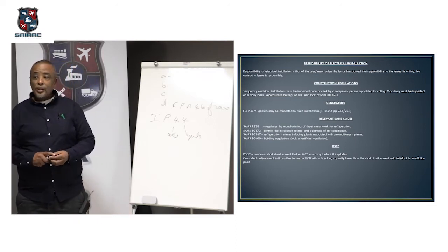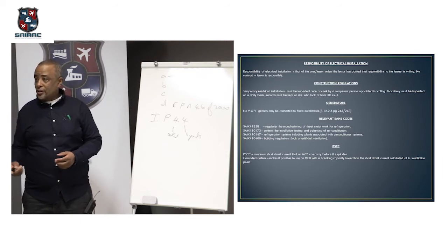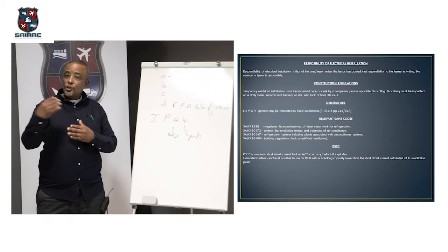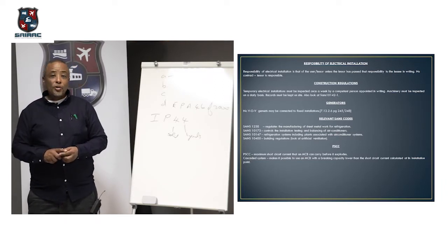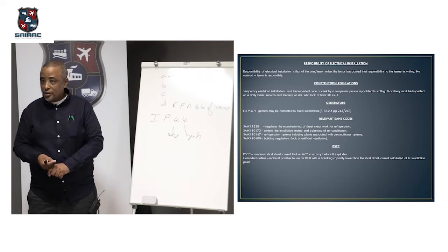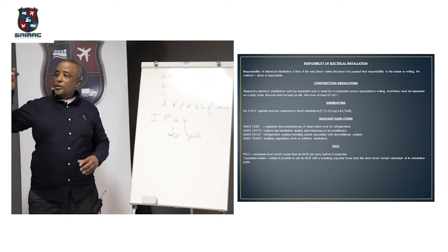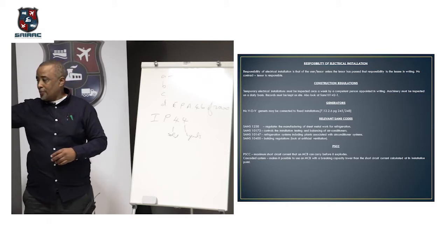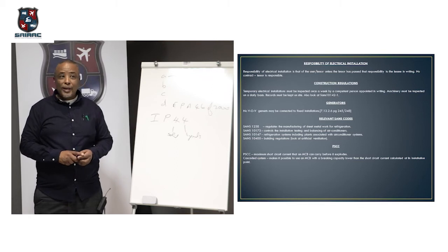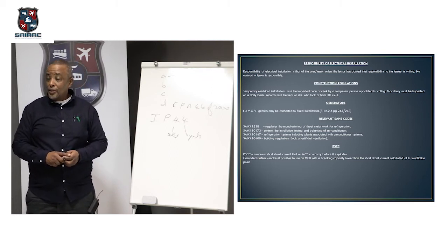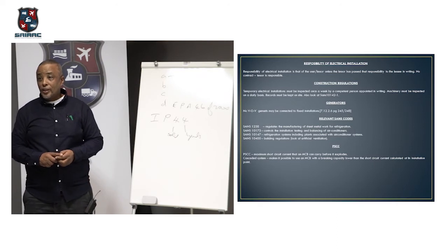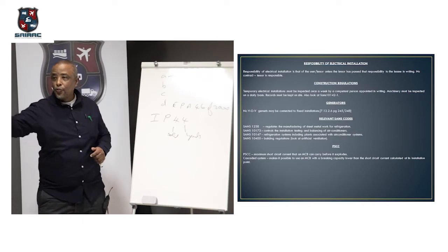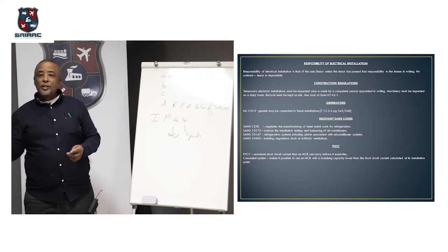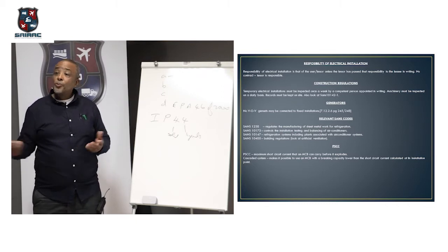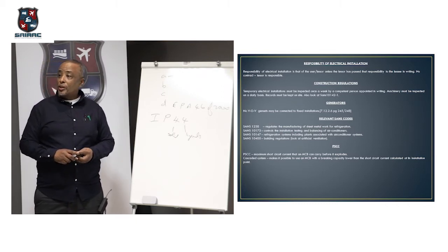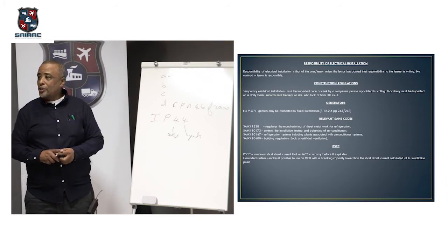SANS talks about construction and demolition sites, very similar. SANS only talks about the responsibility. SANS talks about what the DB should look like. It should be painted orange. It should be robust for site conditions. It must have earth leakage. If you've got one main DB and it's a big site and you've got different sub-DBs, those sub-DBs must be protected by at least a 500 milliamp earth leakage on construction sites. Okay. The reason for 500 milliamps is if the cable is lying on the floor, somebody picks it up, it's got some sort of protection.